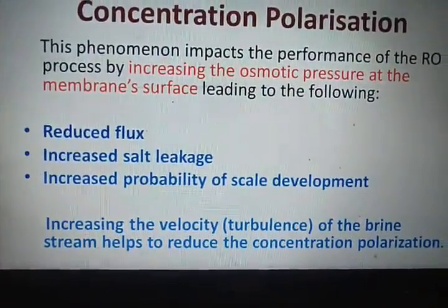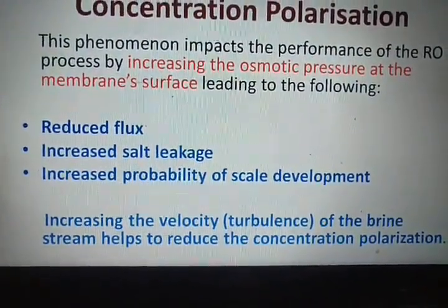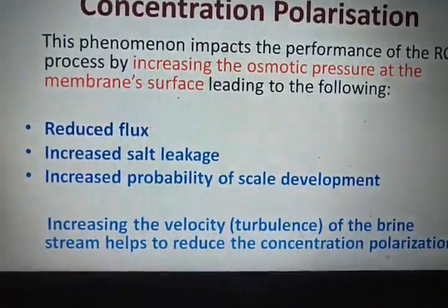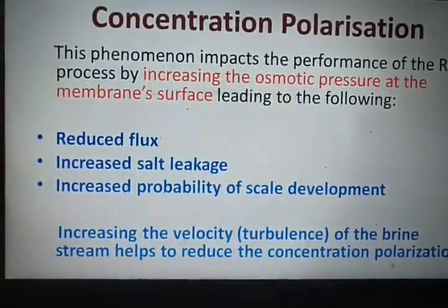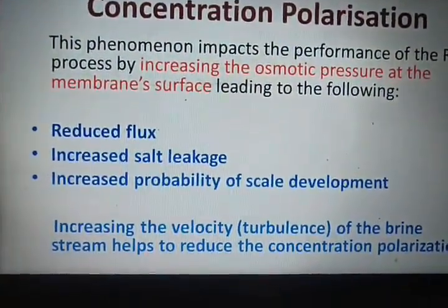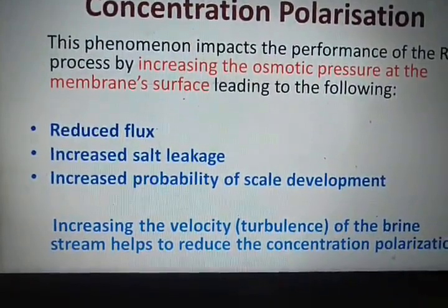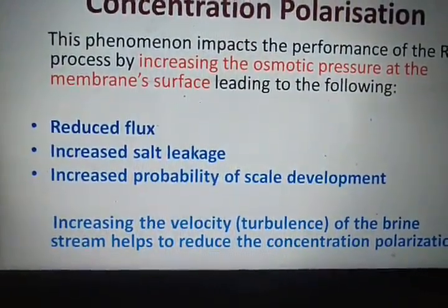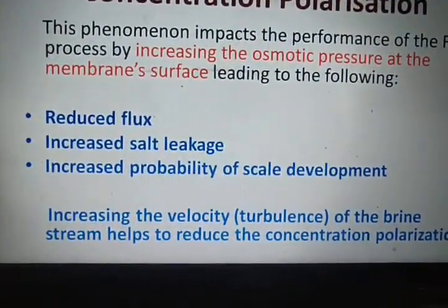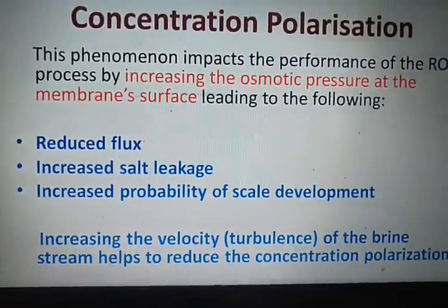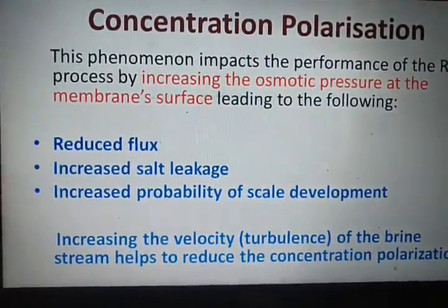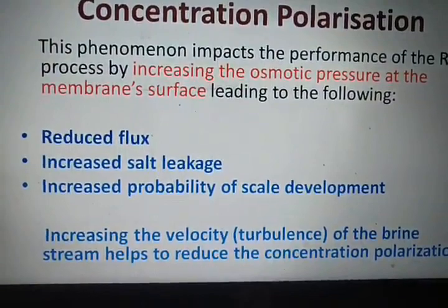naturally it is obvious that it will reduce the flux, that is, the average amount or quantity of water treated per unit area of the membrane per unit time. That is, it reduces flux and also increases the salt leakage, and due to the deposition of the salts, it will increase the probability of scale development on the surface of the membrane.